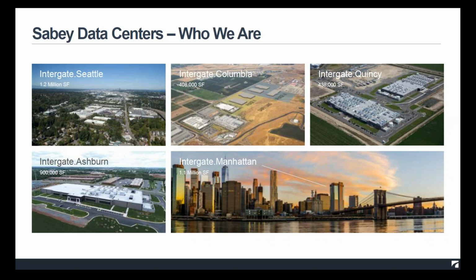And so in the wholesale colocation model, there's essentially two things that our customers pay us primarily. They pay rent, and the rent is based on a per kilowatt basis. So again, it's different than the traditional commercial real estate office where you're paying per square foot. Here, you're really leasing the capacity. You're leasing the power and the cooling capacity along with the space to put your IT cabinets. And then in the wholesale colocation model, the second major payment that you pay to the provider is the electricity. And the electricity is based typically on the metered electricity use, along with the cost for the HVAC and other losses that are required to power that equipment and keep it cool.